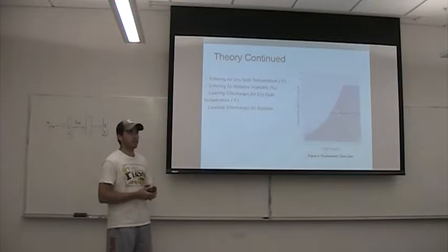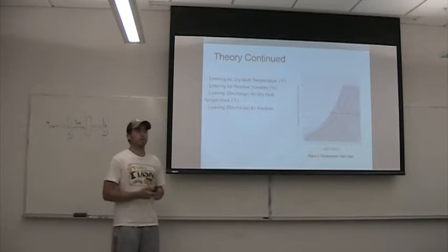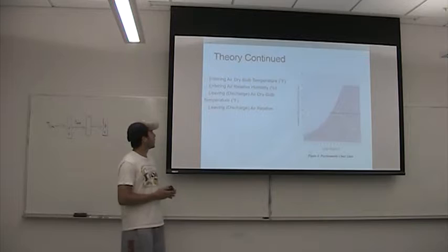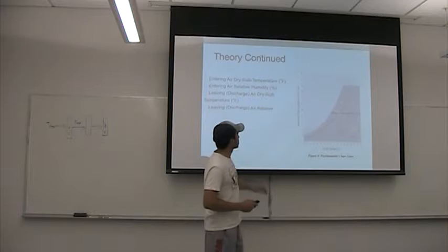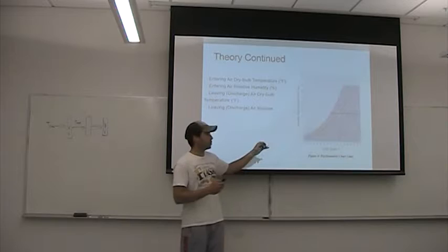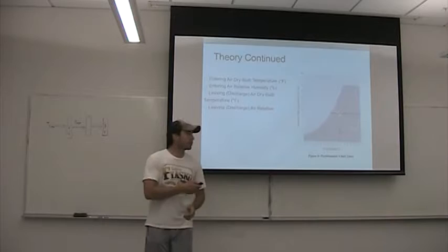What we're going to be finding in this experiment is the air dry bulb temperature, which is just the temperature without moisture or humidity. And then the relative humidity, we'll find that. We're going to find the leaving temperature and the relative leaving temperature. So this chart over here, the psychrometric chart, basically plots all of this: your dew point, your relative humidity. When the relative humidity is equal to 100%, all of your wet bulb, your dry bulb, and your dew point are equal to each other.